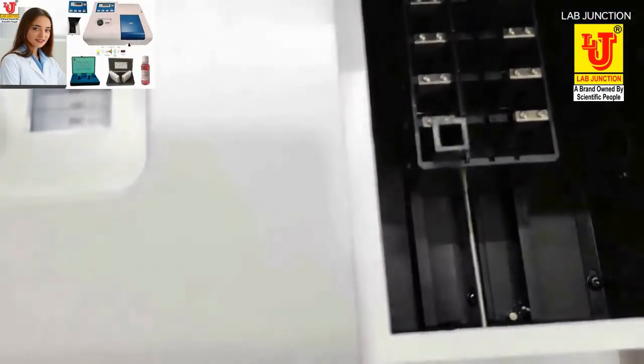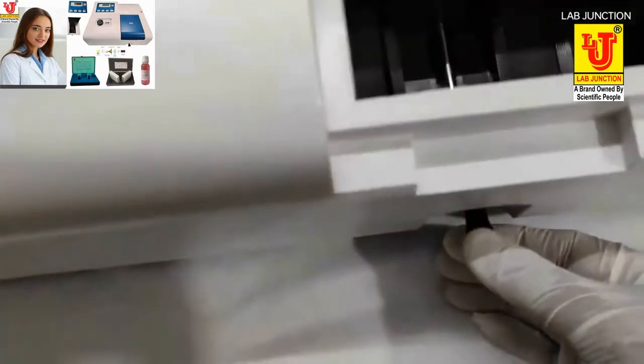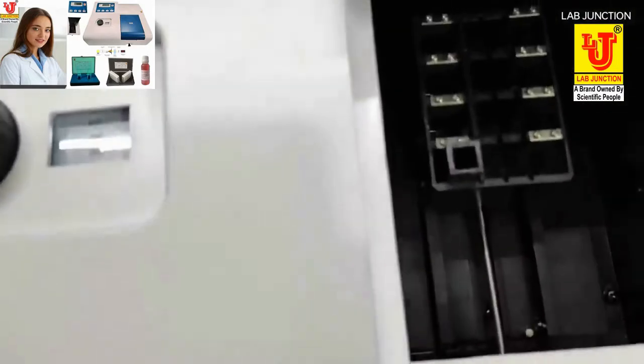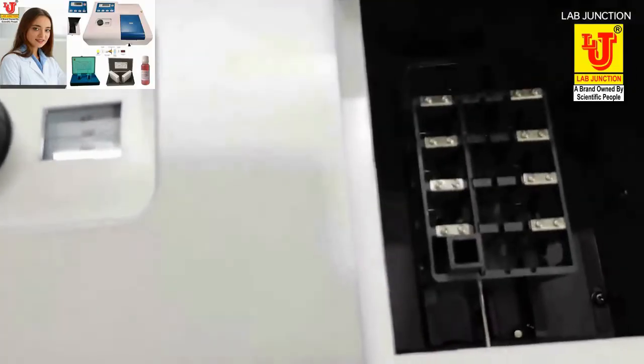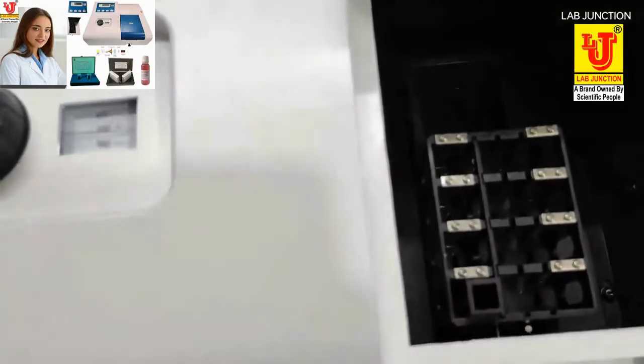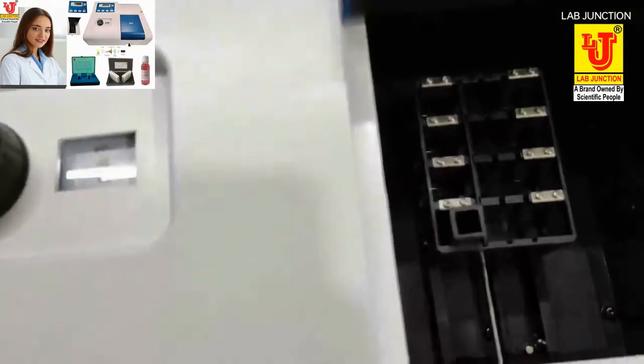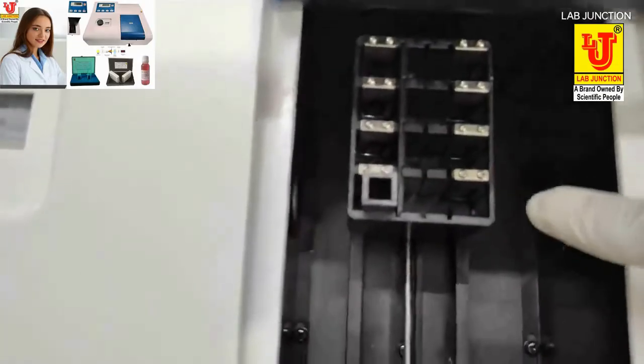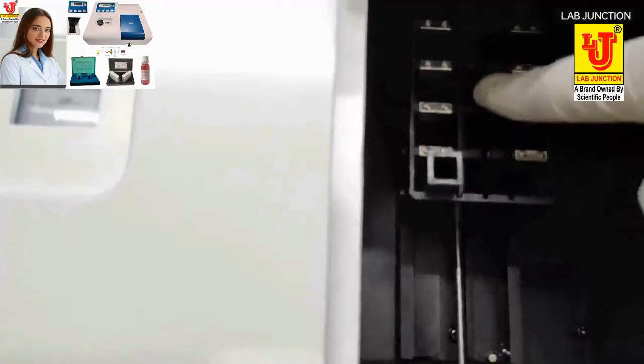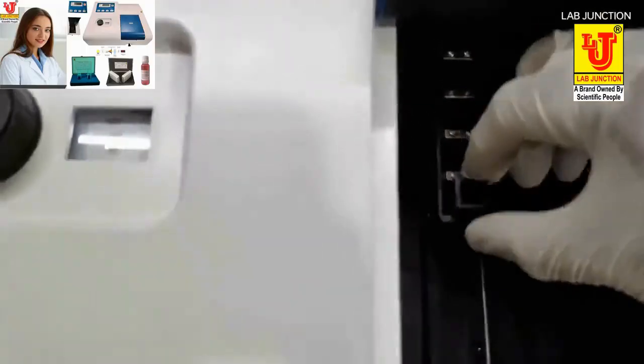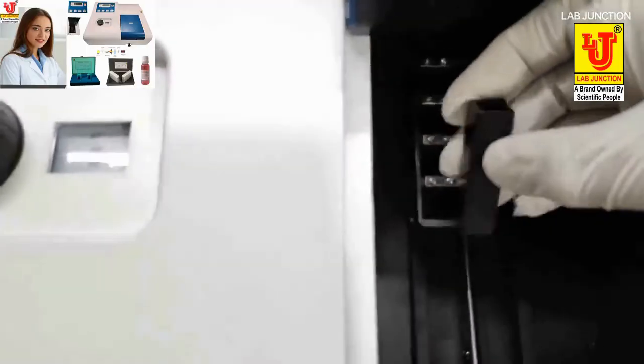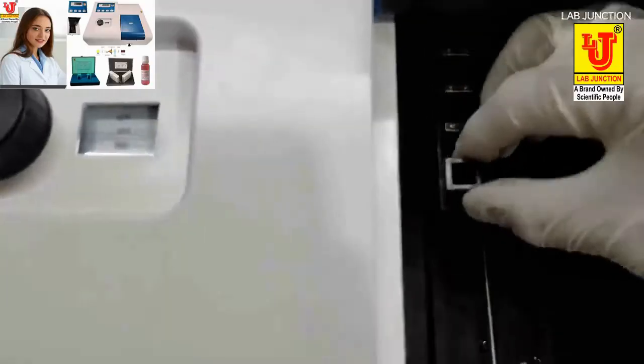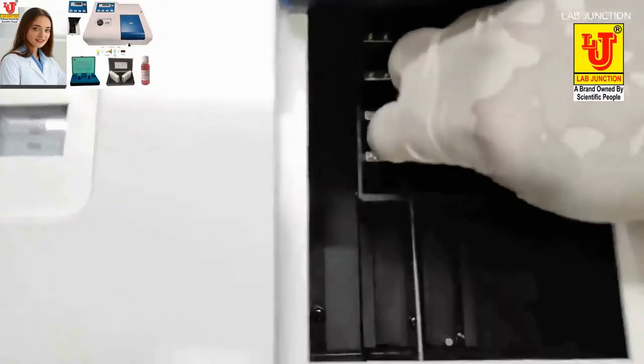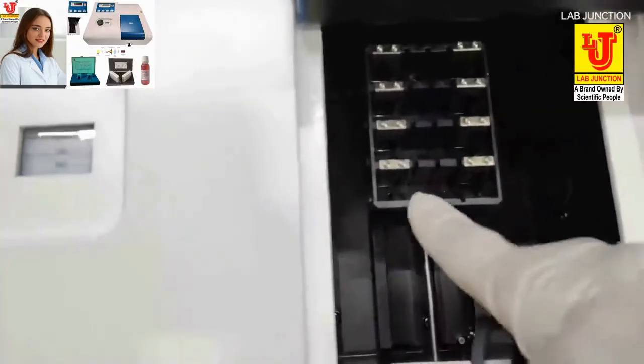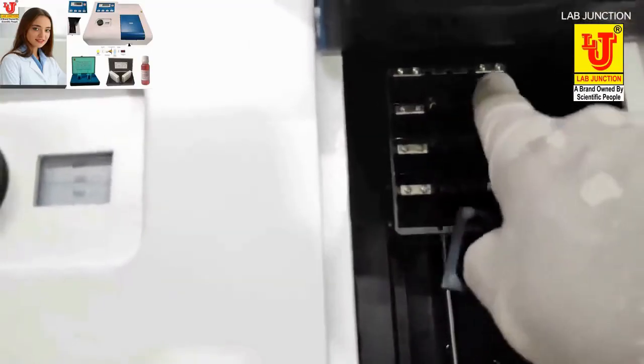Now this is position 1, 2, 3, 4. You can place 4 cuvettes. 1, 2, 3, 4. This is the black dummy or dark current. If you remove this chamber, you can place a 50 mm cuvette there.